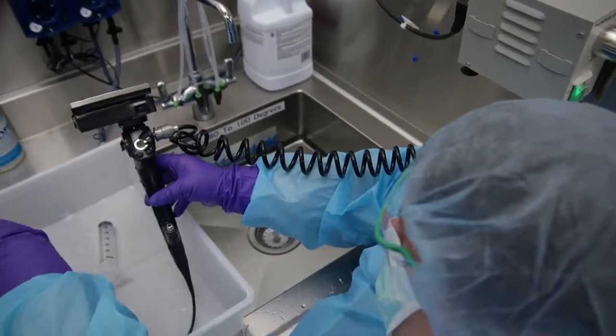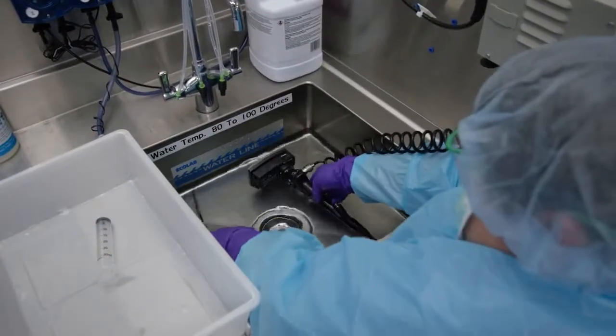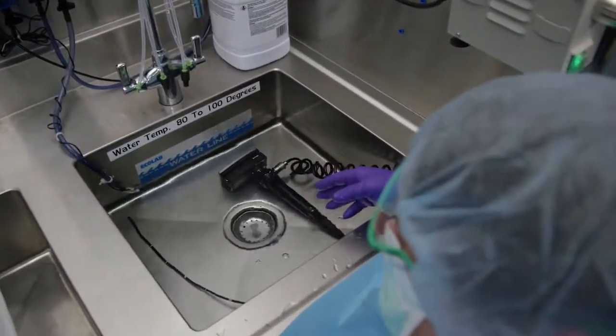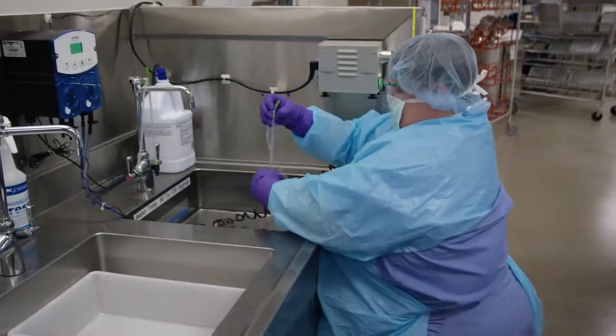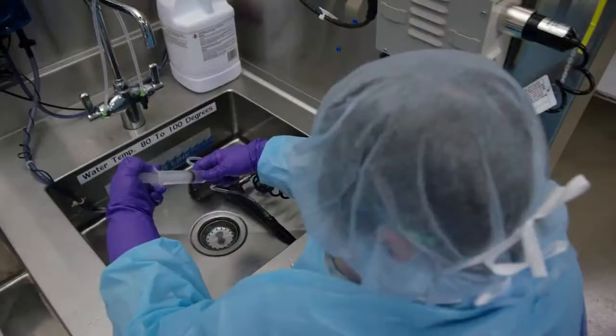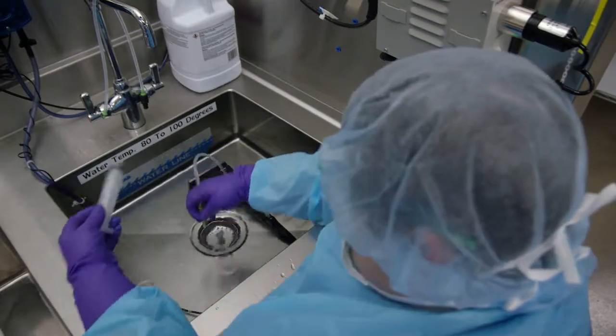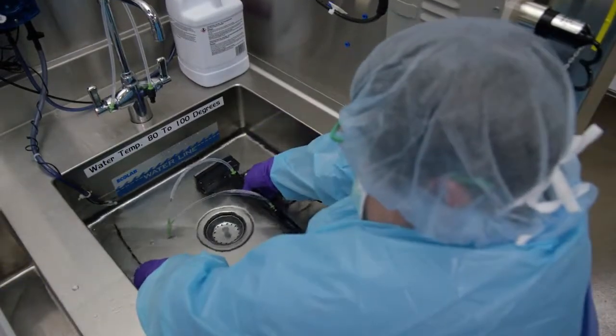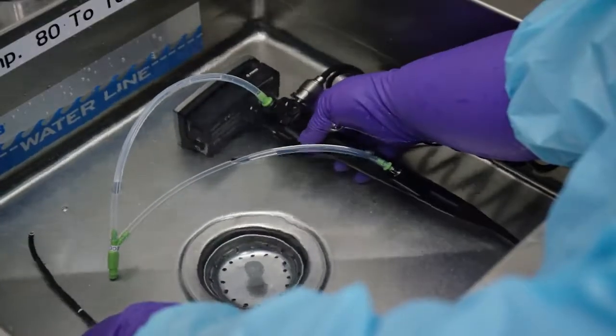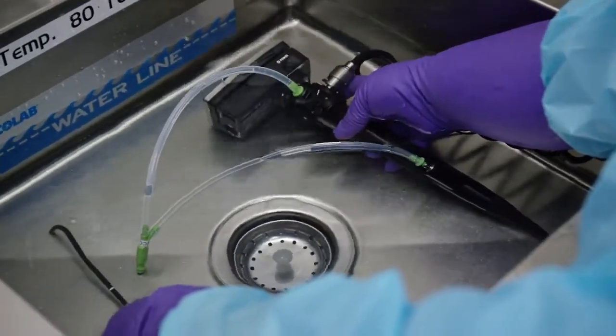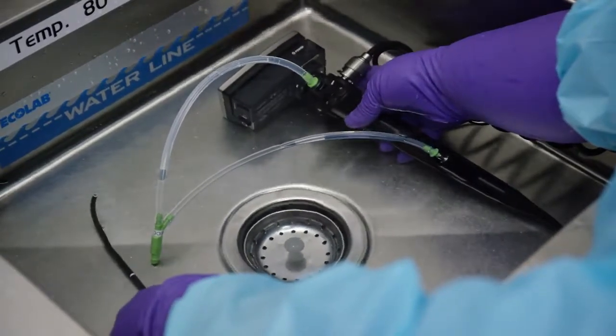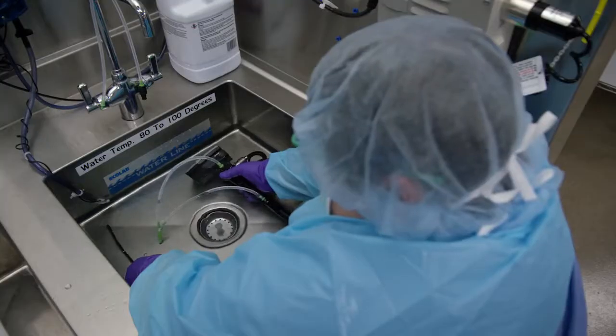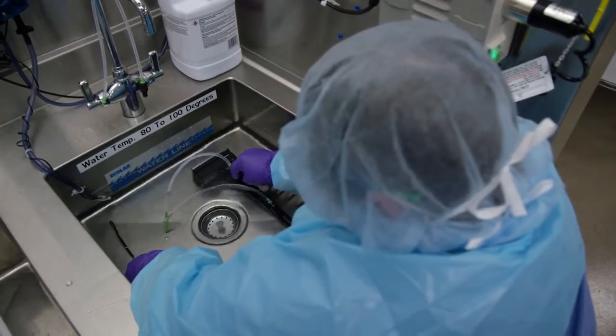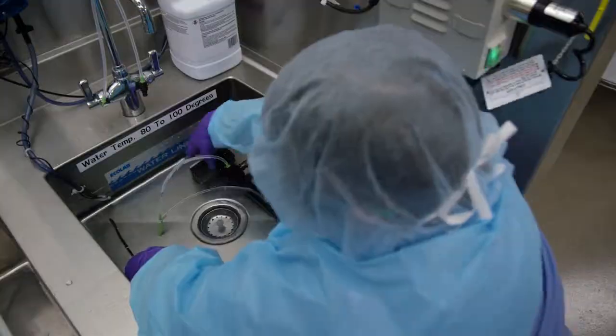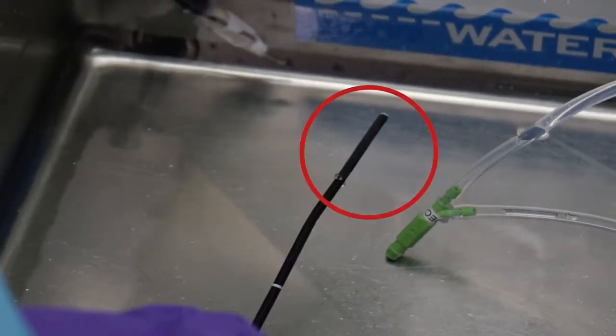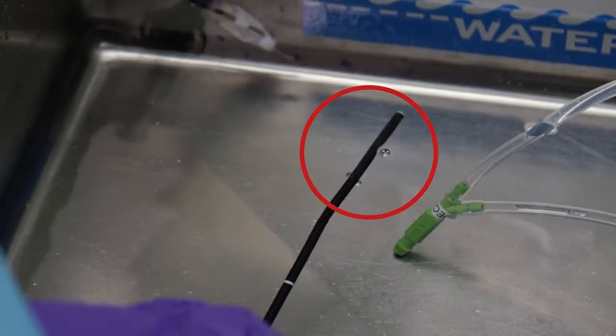IFU. Fully submerge the scope in clean water without detergent and fill internal channels with water. Flex the distal portion of the scope in all directions while observing for bubbles. Observe the control head of the scope while depressing the freeze and release buttons. If O-rings and control knobs are damaged, air bubbles may escape when knobs are turned. Pay close attention to seams and joints. Check the insertion tube and distal bending section, as well as universal cord for bubbles. If a hole is present in the internal channel, air bubbles will exit via the distal tip.